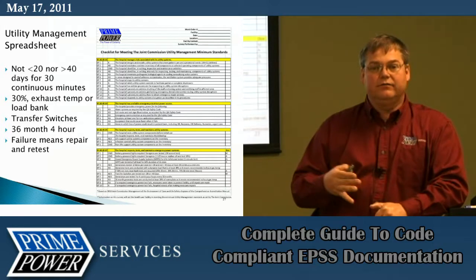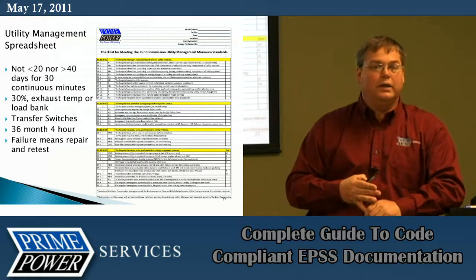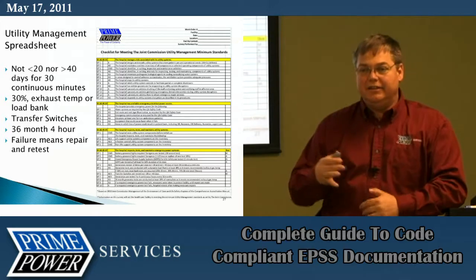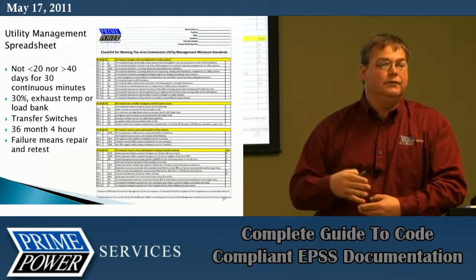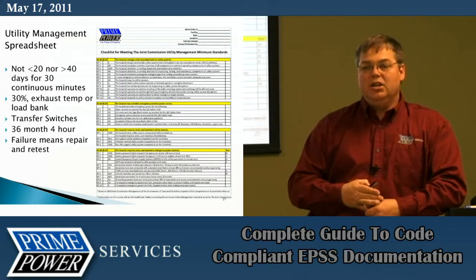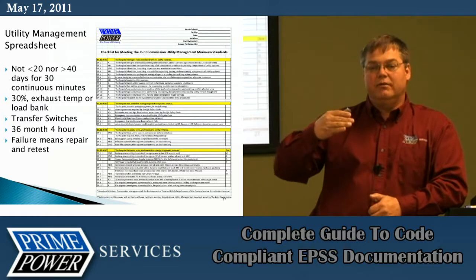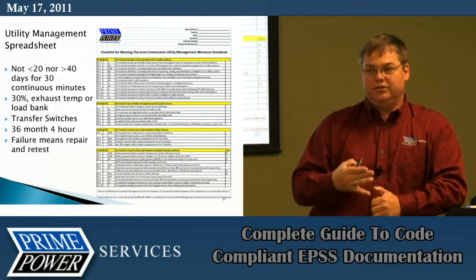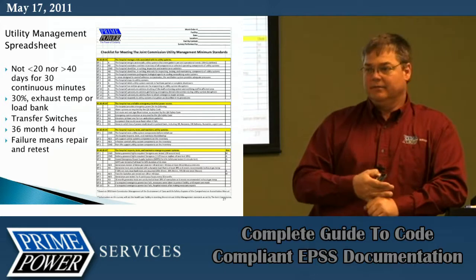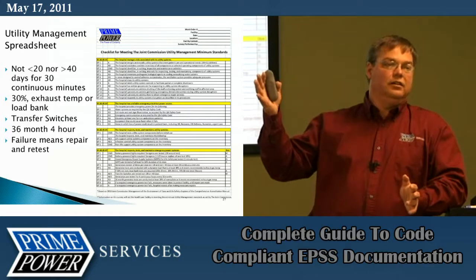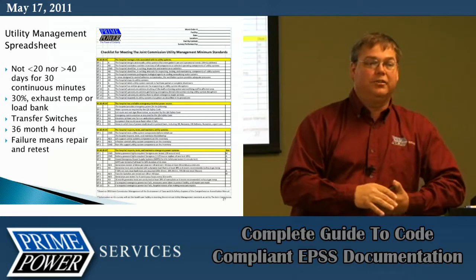Joint Commission, again, from the healthcare side, says the 20 to 40 day rule. The other thing I like to say and teach and inspect on this one is, how do you start that generator test monthly with your transfer switches? Somebody give me a process. So you got, let's pick number 12. You got 12 transfer switches.